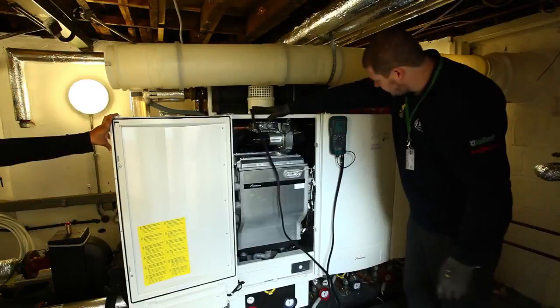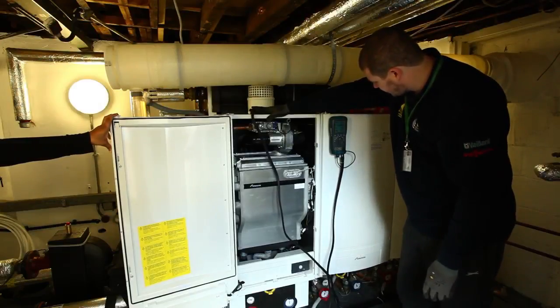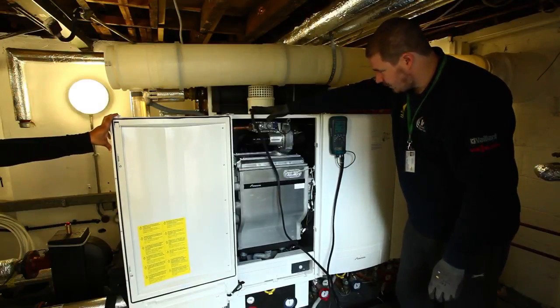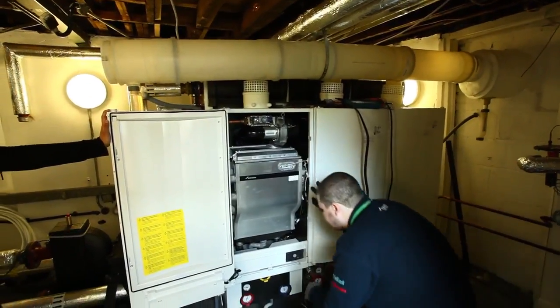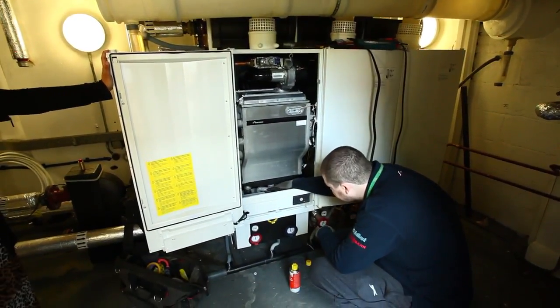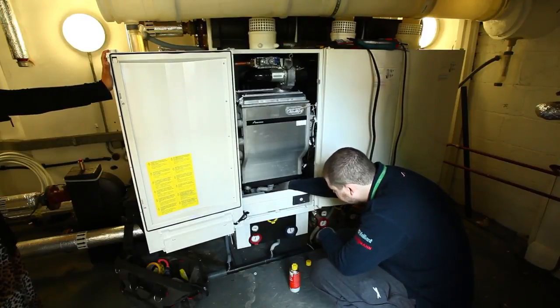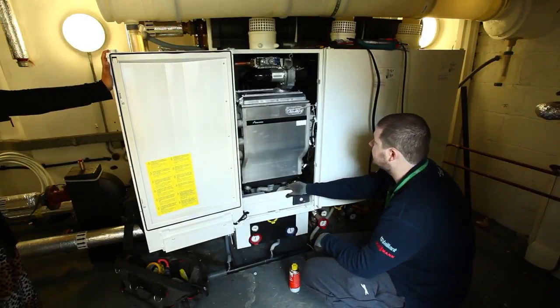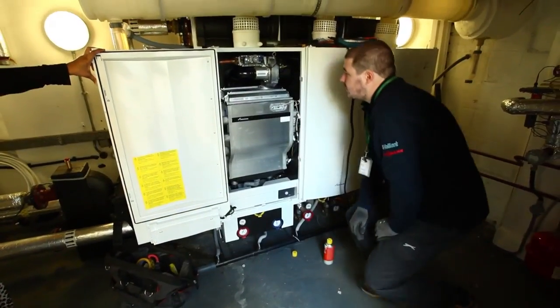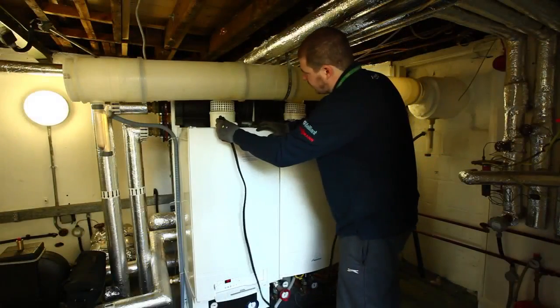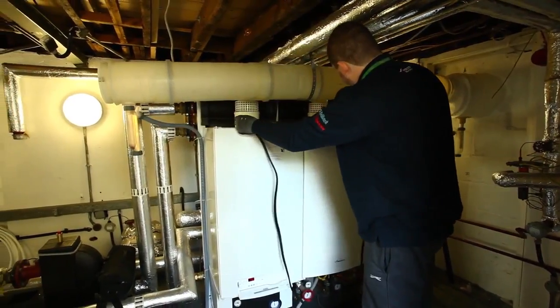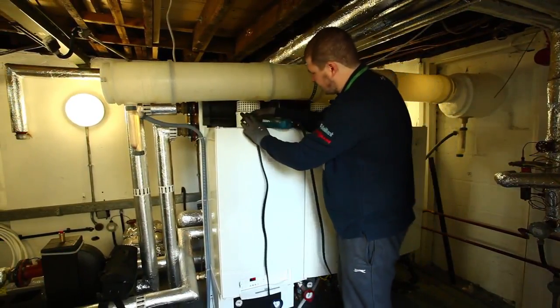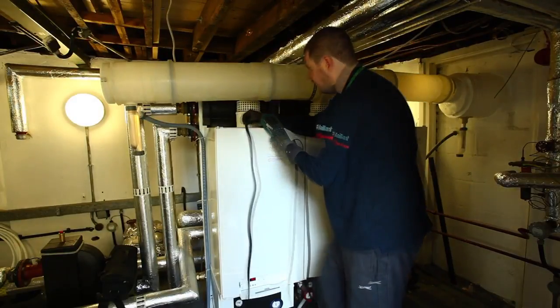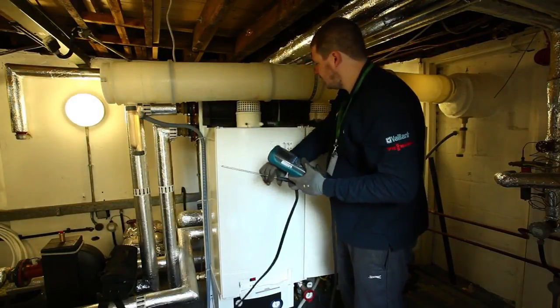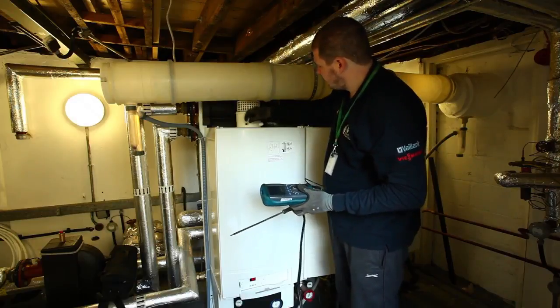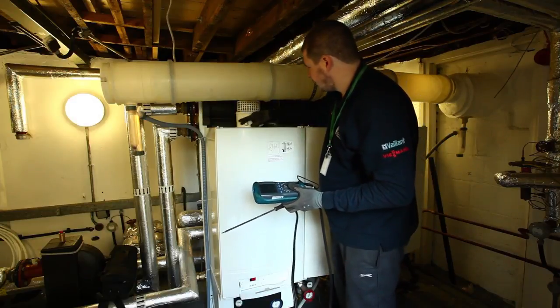Okay, so we're just testing the combustion to make sure that we're getting the good readings off the boiler. Then we check the condense to make sure there's no debris down there. It's not too hot, meaning that the siphon trap underneath it has not failed. And then after that, we close the boiler. We just check our combustion to make sure that we have good combustion and the integrity of the flow. So we're happy with that. We would get a printout and we would fill out a CP15 for the relevant initial commissioning checklist.